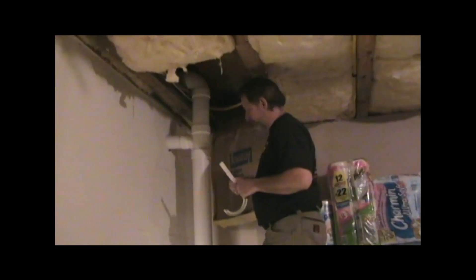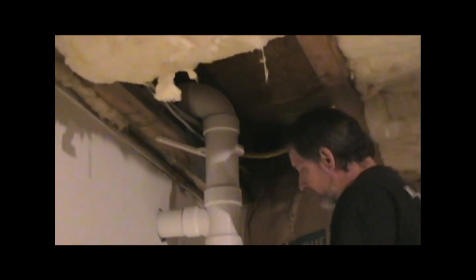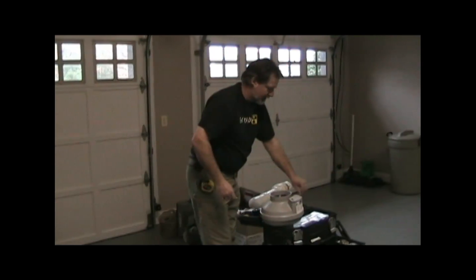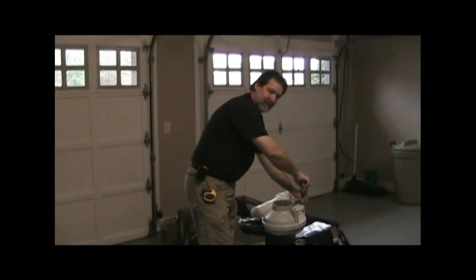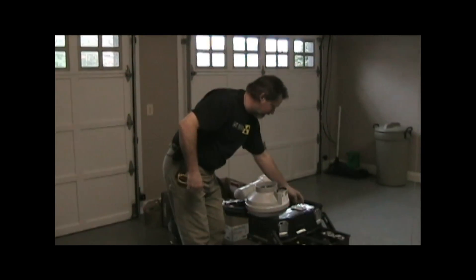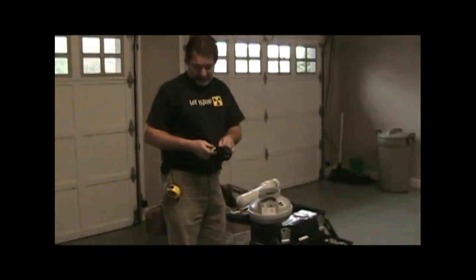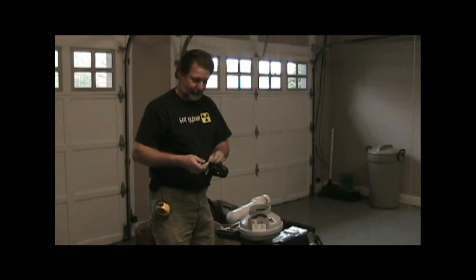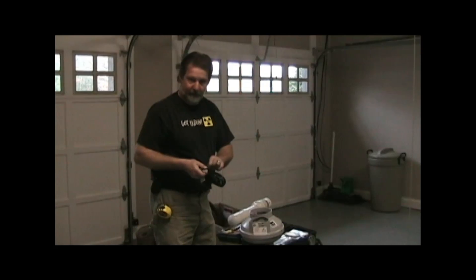I have a plastic J-hook here I'm going to put around the pipe to keep it from moving, making sure it's at the same distance from the wall at the top as at the bottom. We're going to go with a moderate-suction, high-airflow fan here — I think that will be the proper fit, and we'll take a pressure reading to confirm before we finalize the installation. We're installing the fan motor in the garage because we have an outlet there already; no need to get the electrician involved. Normally we put the fan motor in the attic or outdoors, but here it's easy to check on.